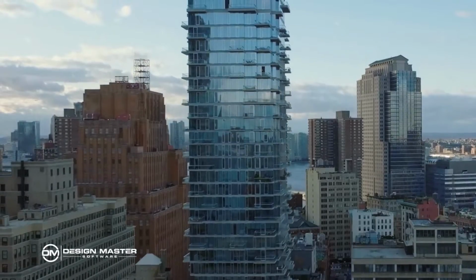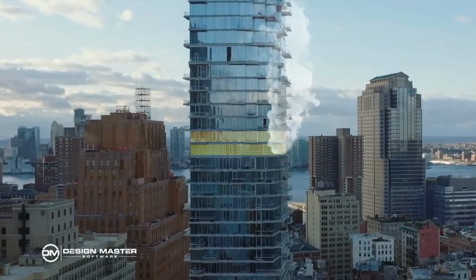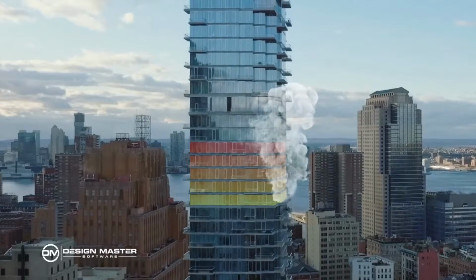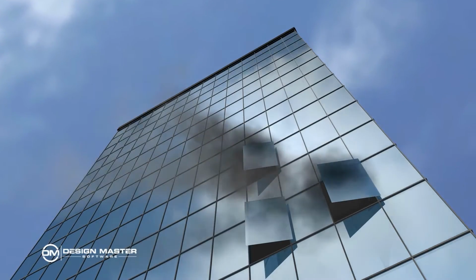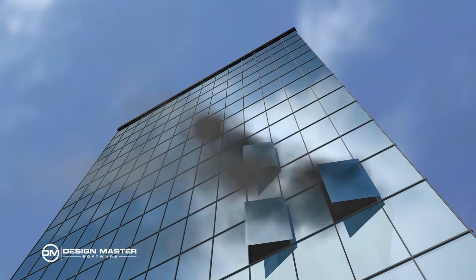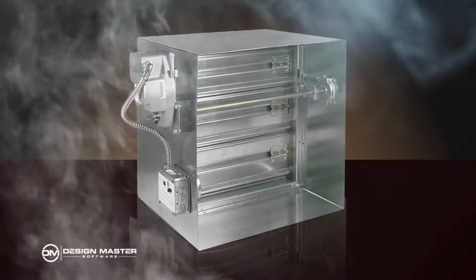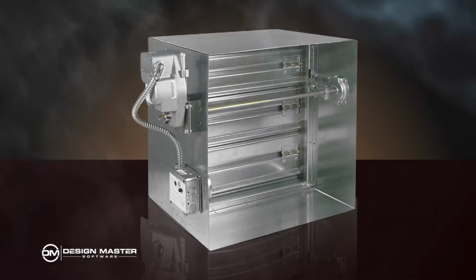A subduct is a clever trick by mechanical engineers to avoid a fire smoke damper in a vertical shaft that goes from floor to floor. And it's not allowed to have openings from floor to floor such that smoke at a fire on one floor can ever make it to the next floor. Okay, that seems reasonable. And you put fire smoke dampers in generally to accomplish this. A subduct got its name because it's a little duct inside a duct. It's 22 inches long, usually about 4 to 6 inches in dimension.